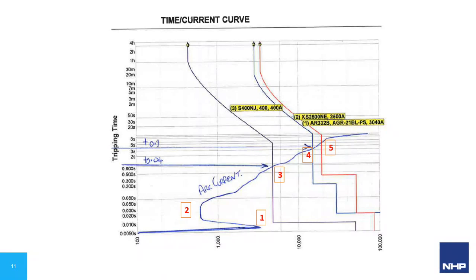So what happens when it comes to arc faults? The blue pen here is our theoretical arc fault current. Stepping through this theoretical one, initially that arc fault current behaves as a short circuit, so you've got a sharp increase, basically linear as shown here. Probably better to use an example. Let's say there's a tool that's been dropped in between the phases. Immediately you've got a short circuit, a very high increase in current in a very short amount of time. So it looks like a short circuit, and that's point number one on the graph.